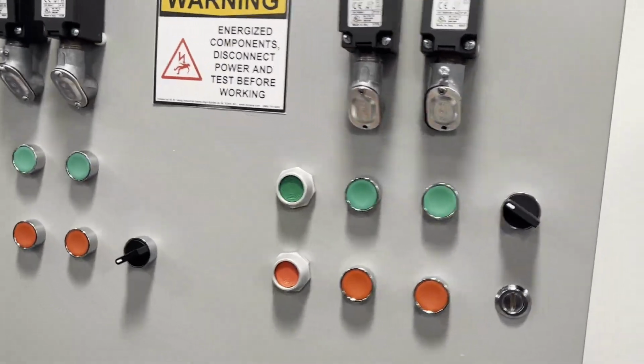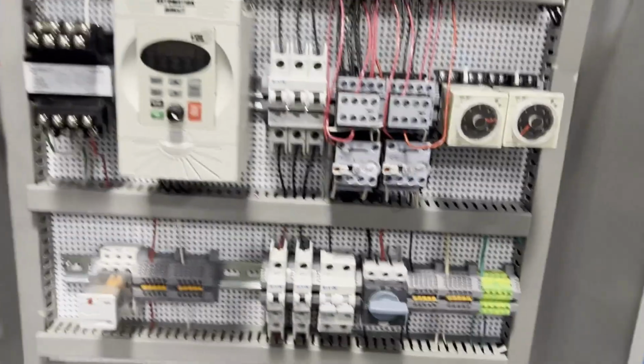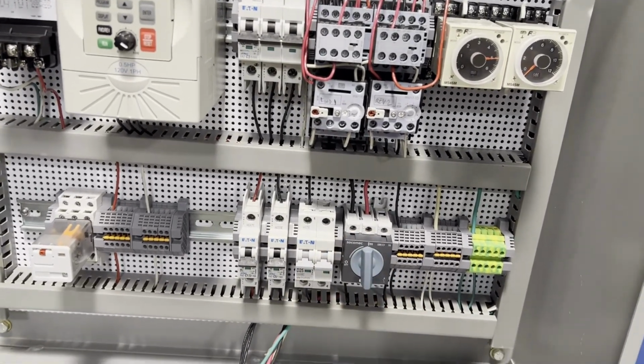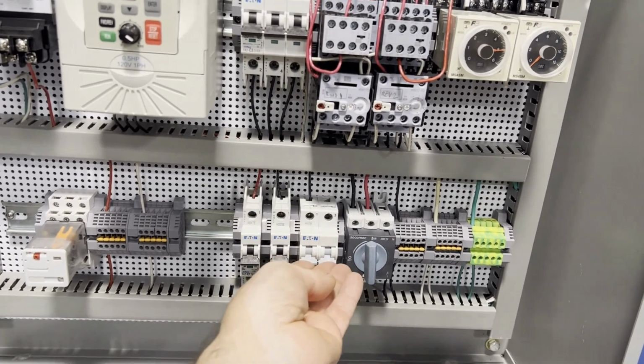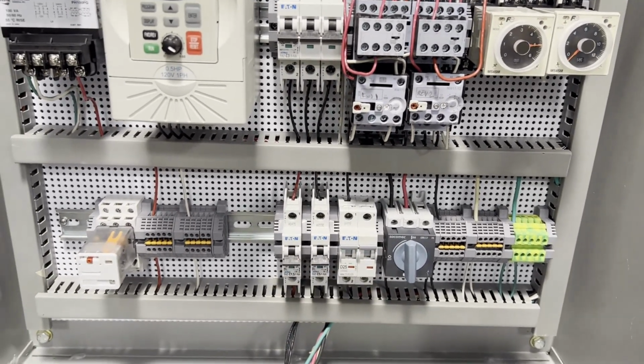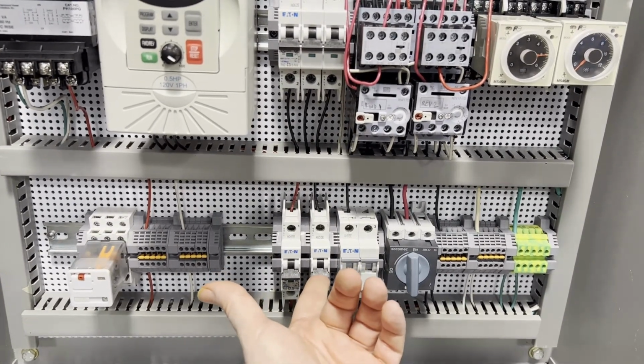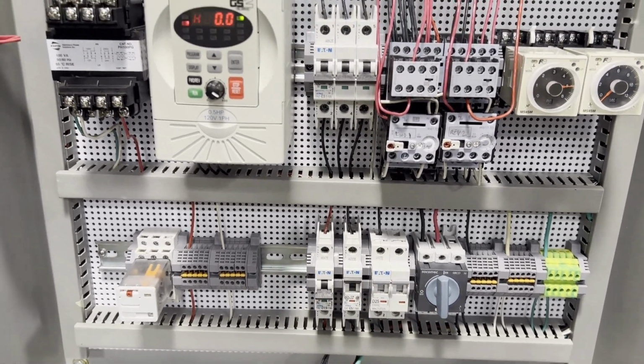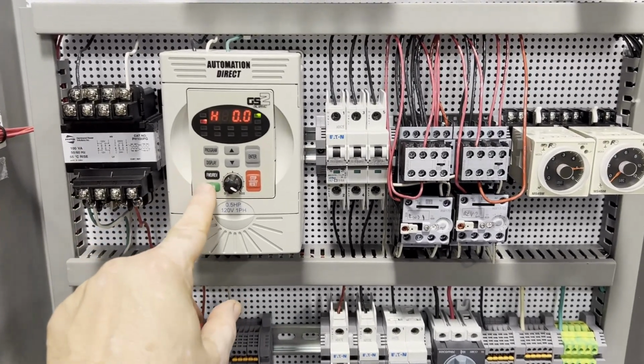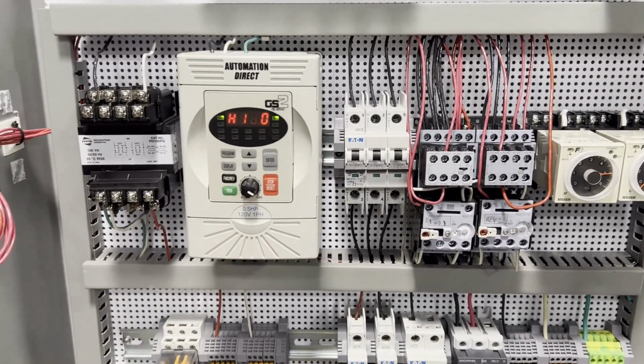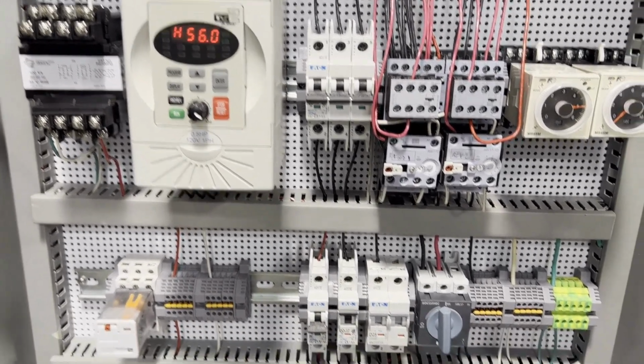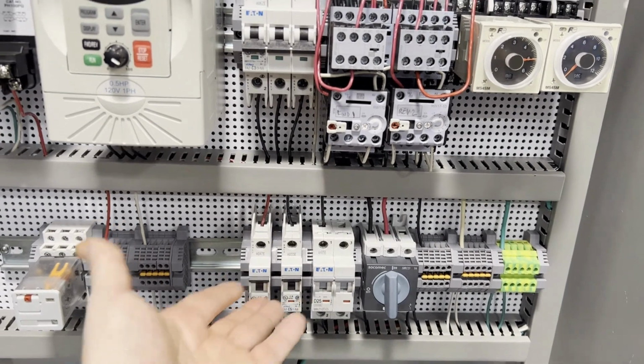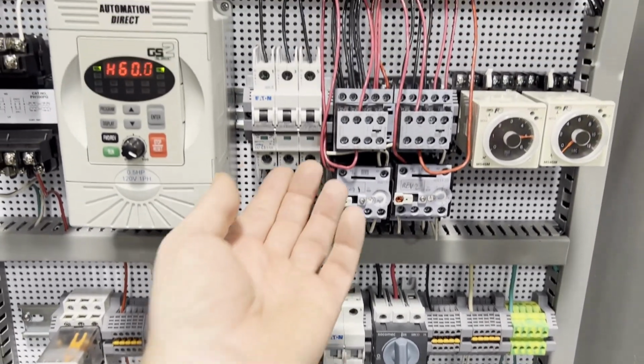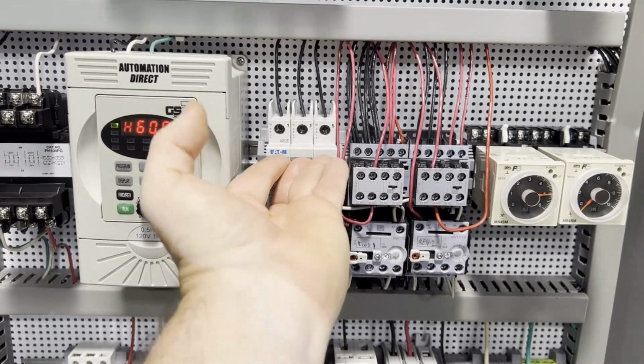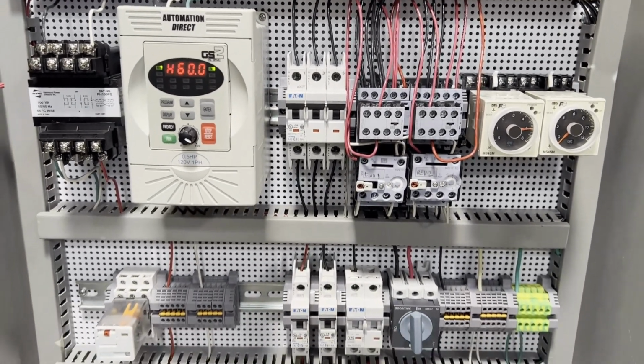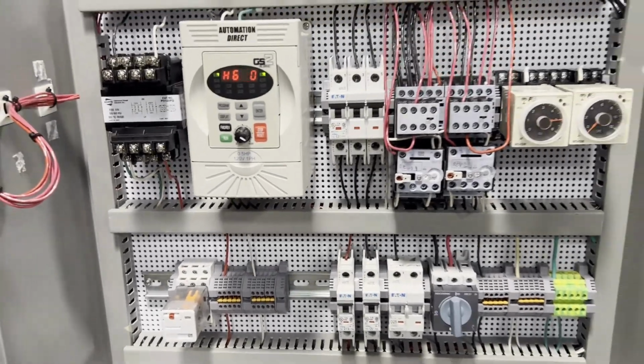Before starting, we're going to power up the cabinet. Close the switch. Close the main circuit breaker. It's a high voltage circuit breaker. It's going to give power to our transformer and our variable speed drive. Our variable speed drive. Control transformer, and we have our three-phase, three-pole transformer, and we are powered up, ready to go.